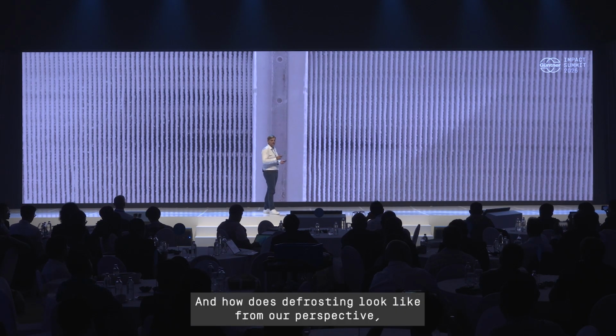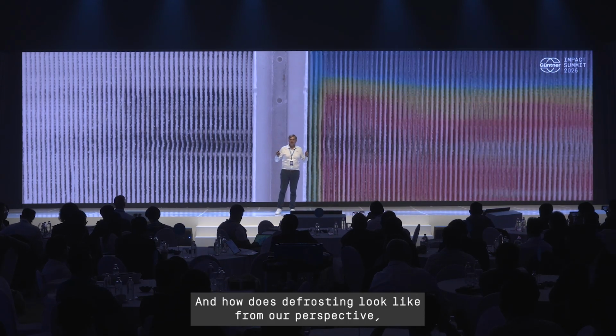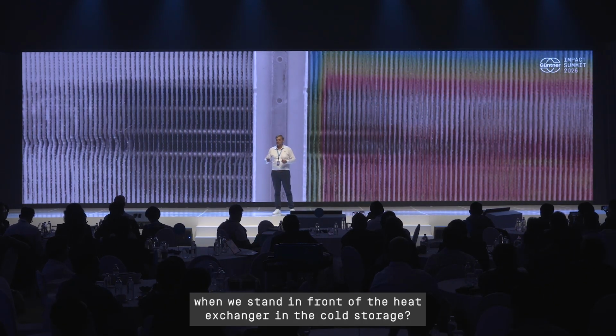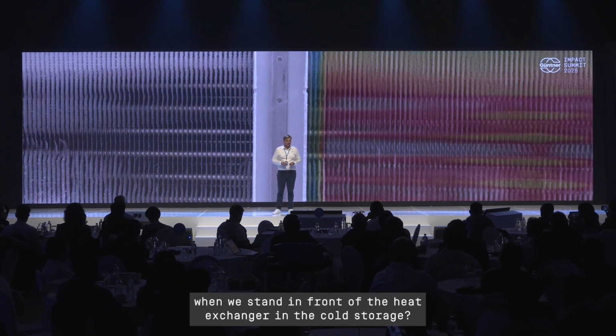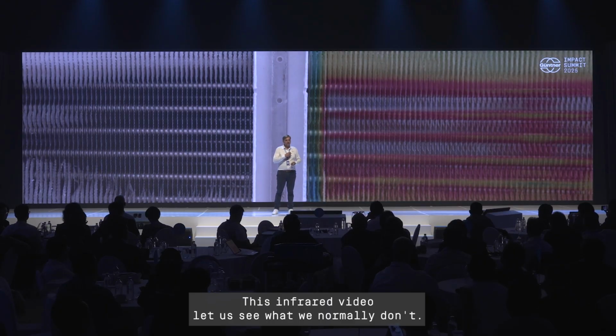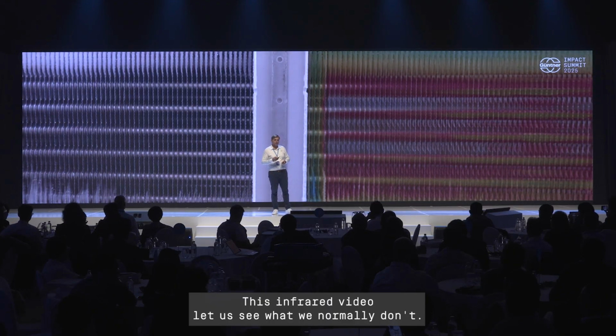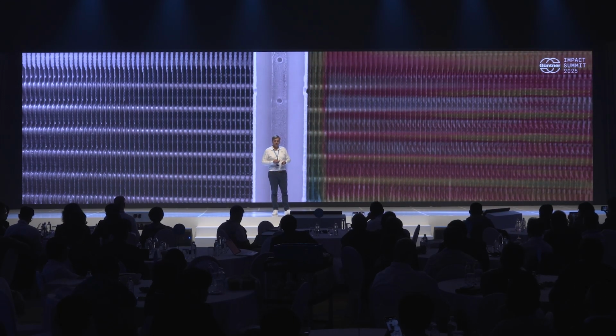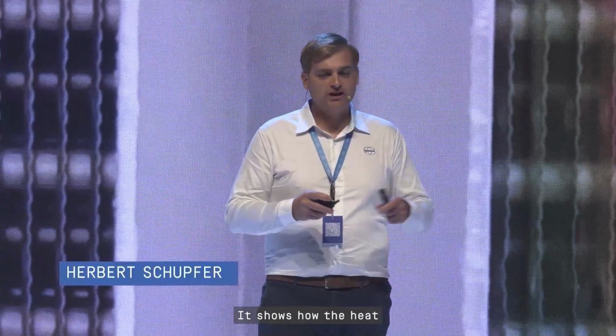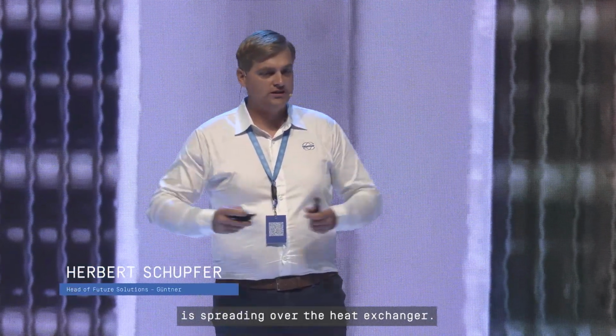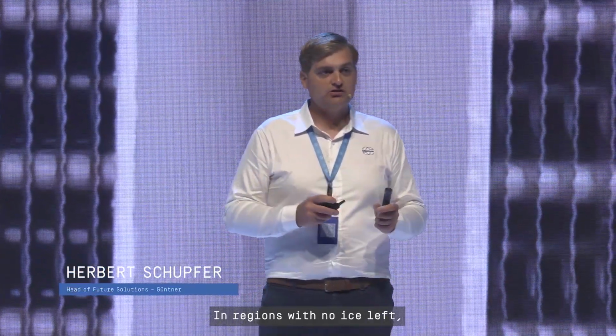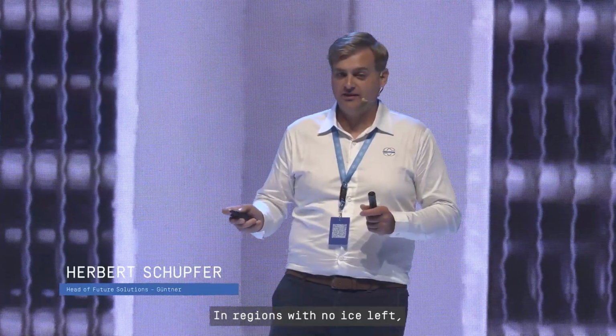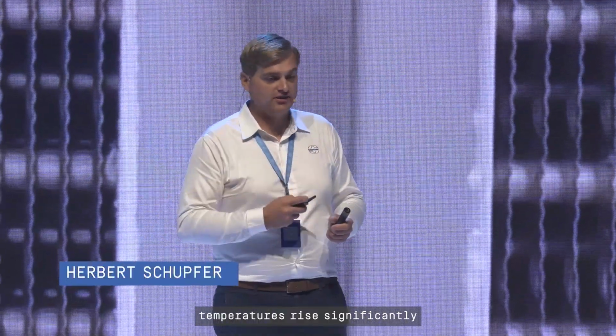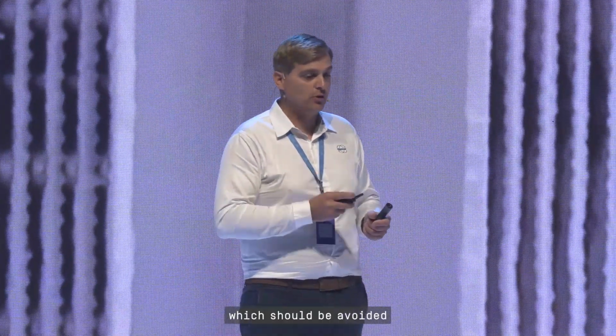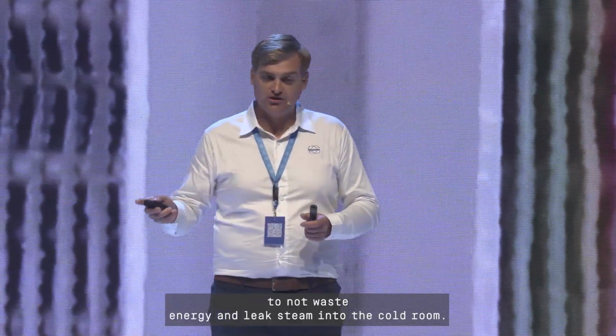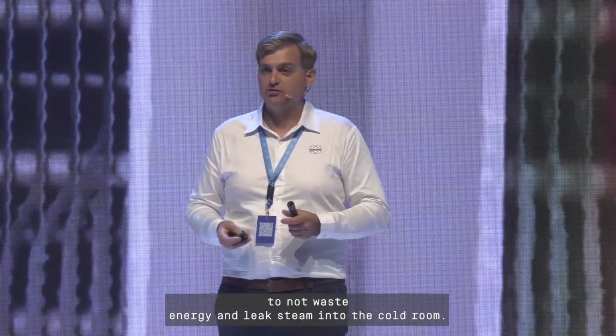And how does defrosting look like from our perspective when we stand in front of the heat exchanger in the cold storage? This infrared video lets us see what we normally don't, showing how the heat is spreading over the heat exchanger. In regions with no ice left, temperatures rise significantly, which should be avoided to not waste energy and leak steam into the cold room.